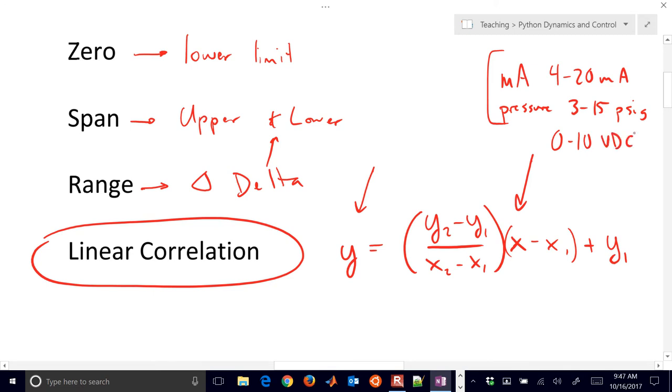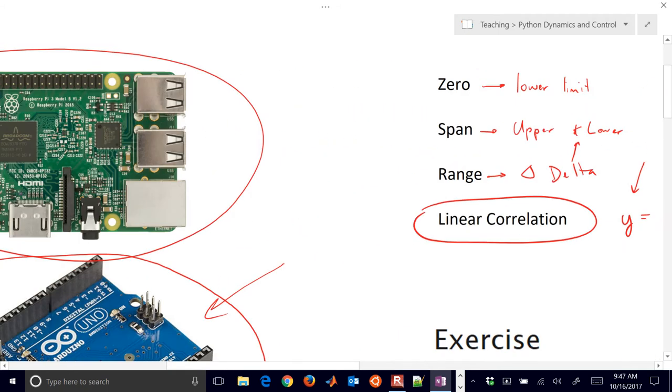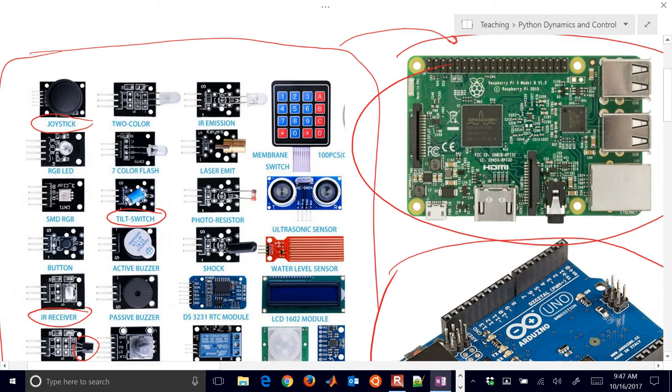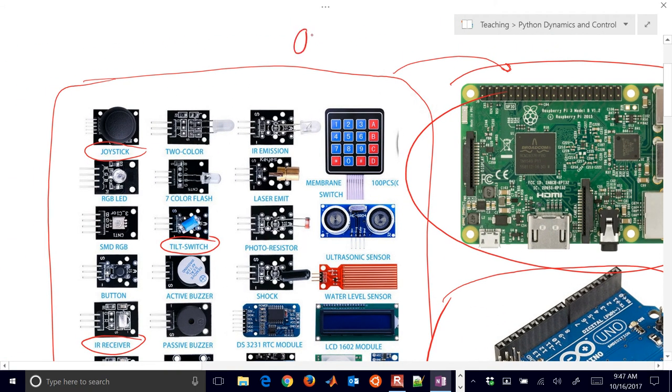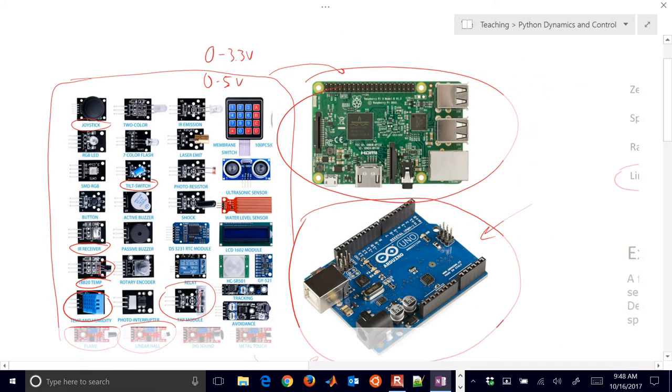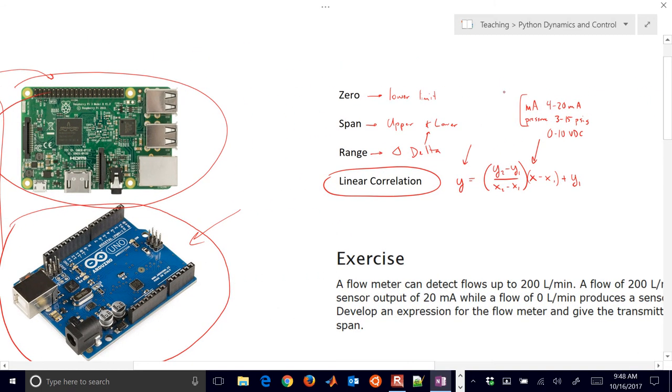There's others that are common. A lot of these sensors that are for the Arduino or Raspberry Pi. These are going to be 0 to 3.3 volts or 0 to 5 volts. So that's for like Internet of Things type applications. These small cheap sensors. For industrial systems, it's a lot of times this 4 to 20 milliamps or 3 to 15 psig. There's a couple other ranges out there as well.